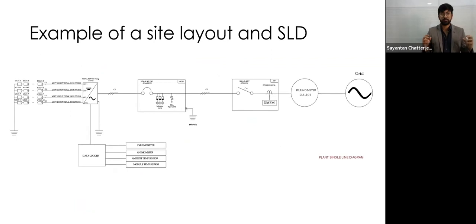I think it's very small to see properly. In the extreme left there is the solar module; that's the symbol of solar modules. That means these 18 solar modules are connected in a single string, and after that it goes directly into the inverter. But in small-scale plants like 5 kilowatt, 10 kilowatt, 20 kilowatt, we use an ACDB or AJB, array junction box, or AC distribution box. This AJB provides us protection. In the array junction box, we provide DC side SPD along with fuses and isolators.